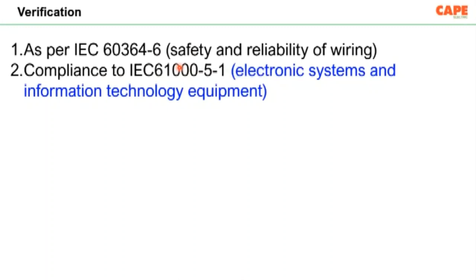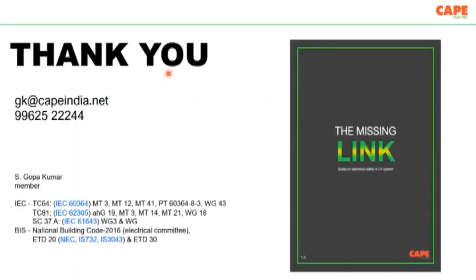I'm talking about the testing of the entire system, starting from probably a UPS and all the items connected on the electrical network. This testing is also compulsory. Most of you know this: IEC 60364, 10 tests are recommended in our IS 732, but mostly we don't do it. Similar is the situation for the EMI test. Mostly we are not following.